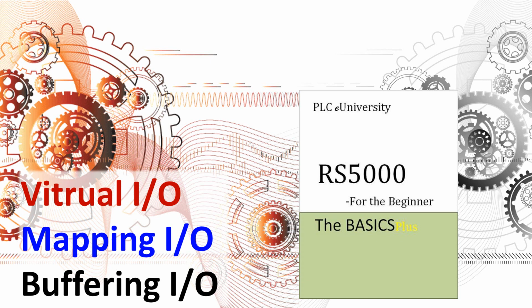With 5000, that's not the case, because the I/O modules are smart, at least they are for ControlLogix, the 1756 I/O modules. And besides that, CompactLogix, which uses the 1769 I/O, along with Point I/O, although those I/O modules are not smart, the chipset in the CompactLogix processors has a separate chipset that can collect the I/O basically on an RPI, which means that the input image gets updated completely independent of the scan of the program.